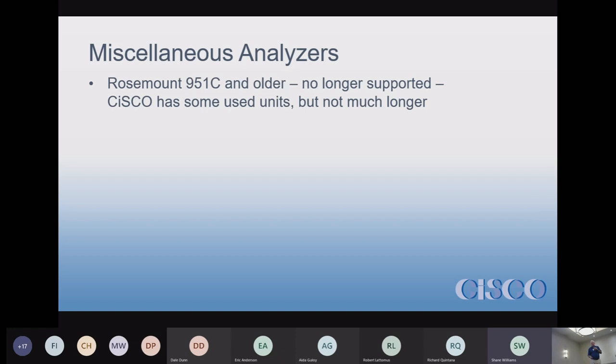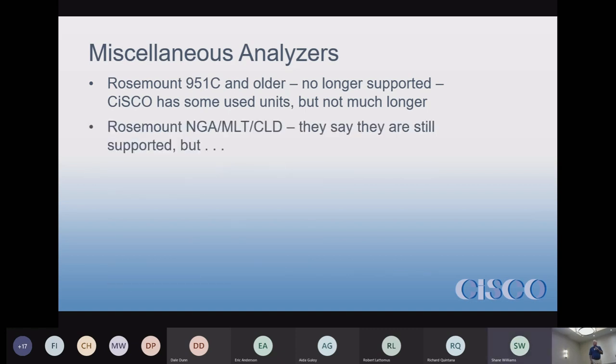The Rosemount NGA, MLT, and CLD analyzers — depending on which version you have — technically Rosemount says they still support them, but plants that have those tell me support is not very good. On a technical basis they're still supported, but in reality they're not. If you have those, it's time to budget to get rid of them. They're a multi-component analyzer with all components measured in three different boxes that all feed into a central brain.